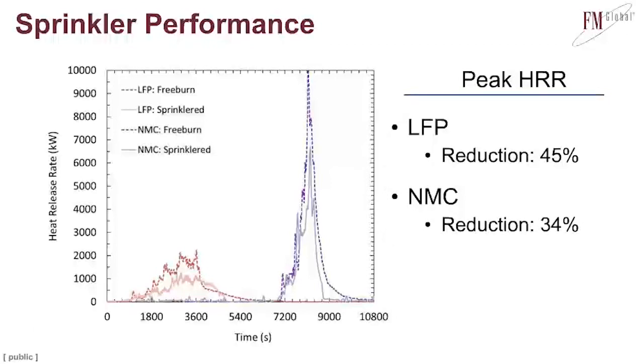And if we look at the reduction in peak heat release rate, the iron phosphate system was reduced by about 45% by adding sprinklers, and the NMC system was reduced by around 34% by adding sprinklers. So these are appreciable reductions. I do think it's important to ask the question of who cares? 45% or 34% of a large number is still a large number. So what is the value in that reduction? The value of that reduction is how this data is used.